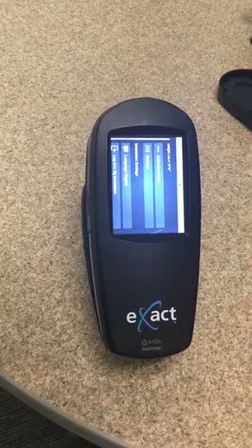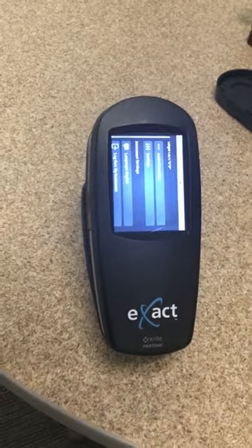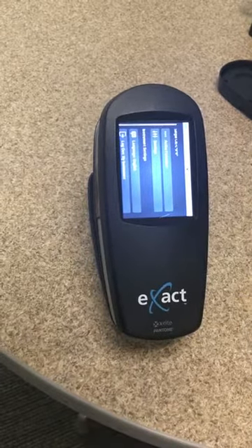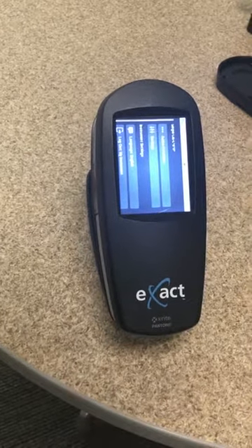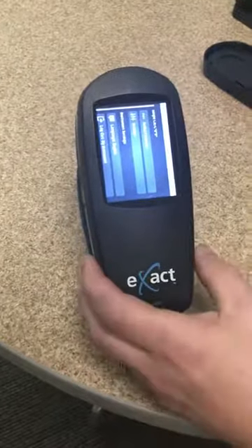But that will automatically calibrate. So if you leave the instrument in an up position, about every 24 hours this instrument will ask to be calibrated and it will go through a calibration procedure. It could be sitting on your desk plugged in or just sitting there and all of a sudden the instrument will take off and start taking measurements. It's not possessed — it just realizes it needs a new calibration and will go do a calibration on its own when it needs it. Well, thank you so much for that overview and we'll dive into some more features in the next video.